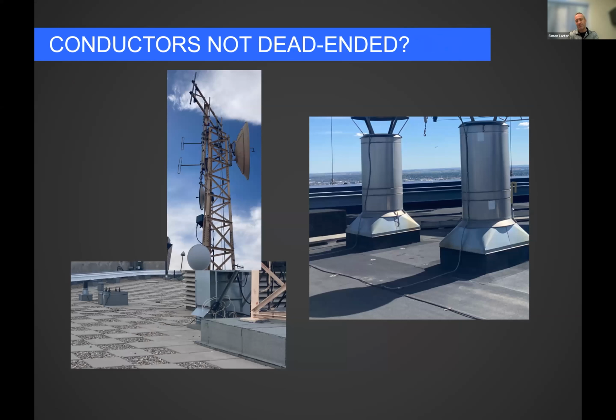Conductors not dead-ended here. This one's kind of hard to visualize sometimes. I did talk about it way up top with the lightning rod that was glued on the parapet top. But here's an example from the Bow Tower. Hey, now you're getting the view from the top of the Bow Tower too. I'm just taking you on a tour of all Alberta's tallest buildings. But see down at the bottom of those vent fans there, there's a short horizontal run of cable that comes over to the main conductor across the roof. We call that a dead end. The drop from the lightning rod at the top all the way down there.